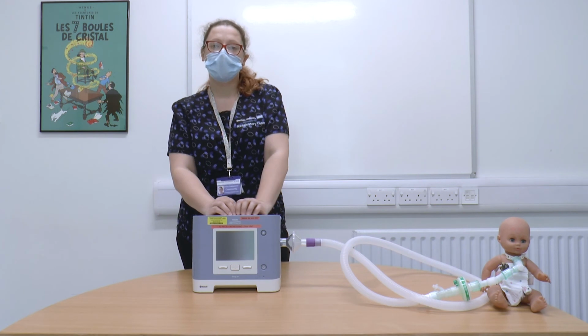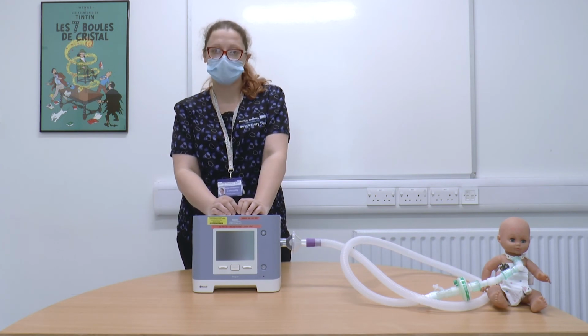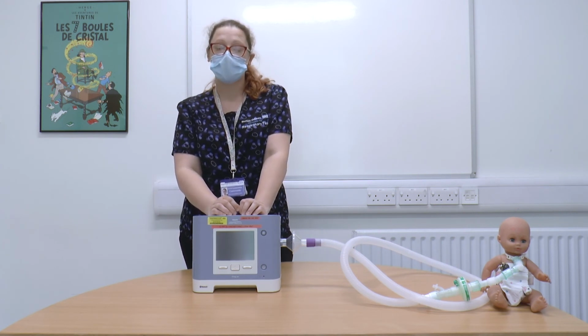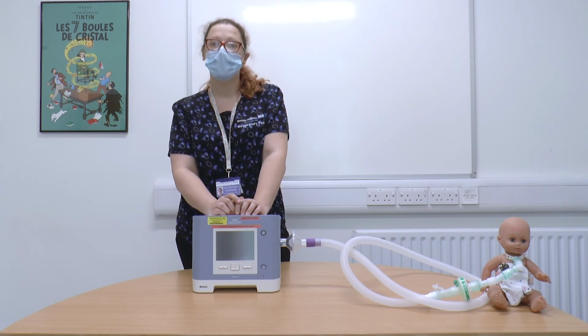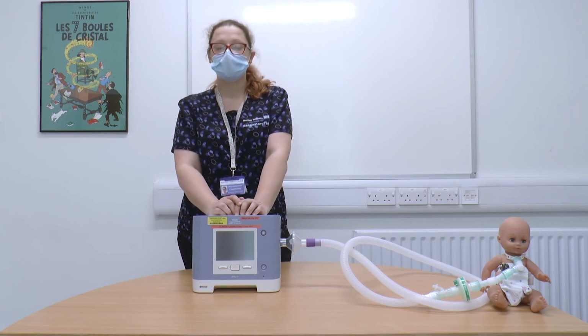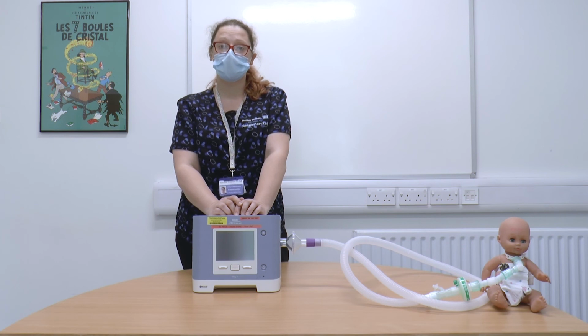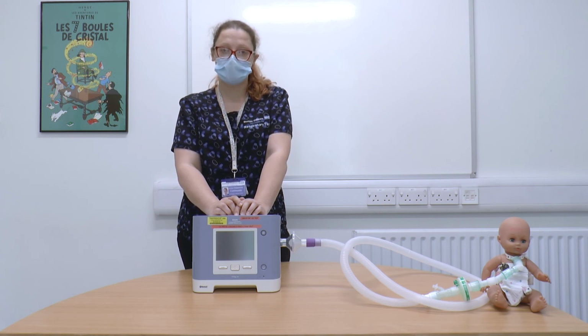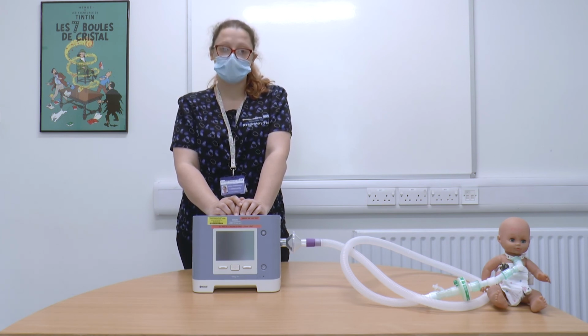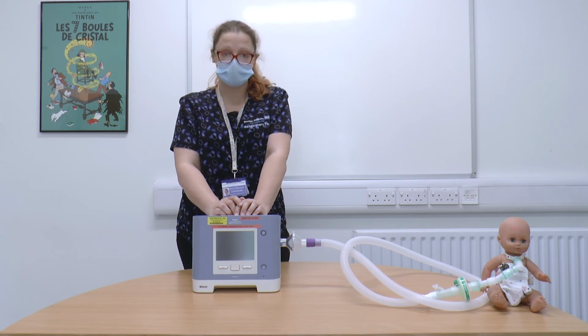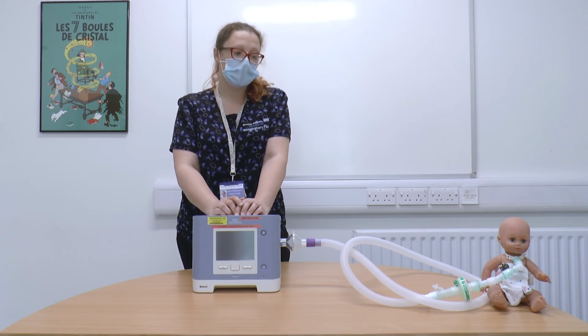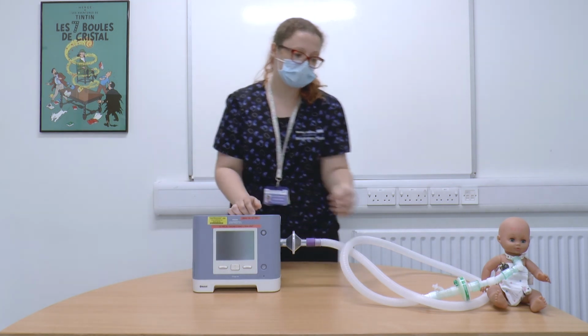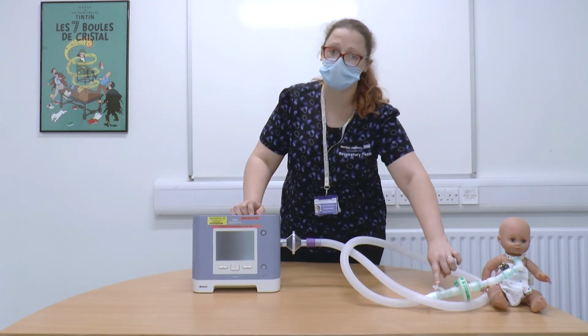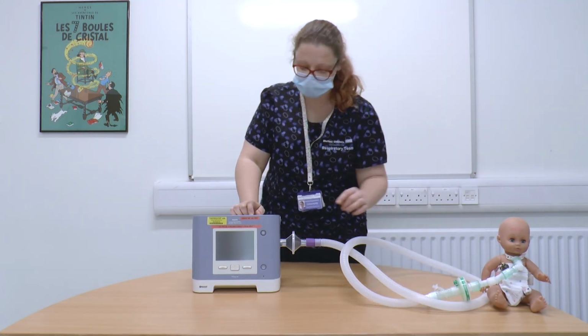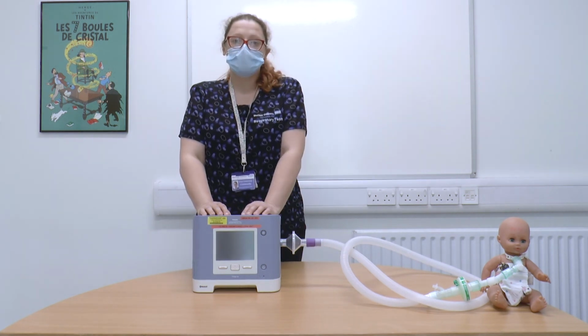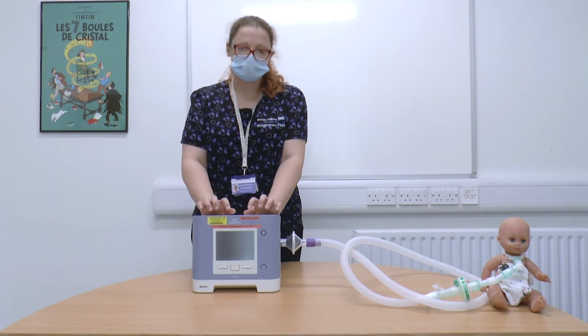The other alarms are high alarms, so high flow, circuit disconnection, high minute volume, high tidal volume. The machine is trying to tell you that the child is either breathing too fast or no flow is getting into the child because air is escaping. Again, start with your child. Check the tracheostomy is in situ, check the tubing is attached, work your way backwards to the vent, check the oxygen port is on if you have no oxygen being delivered, and then check that everything is attached.